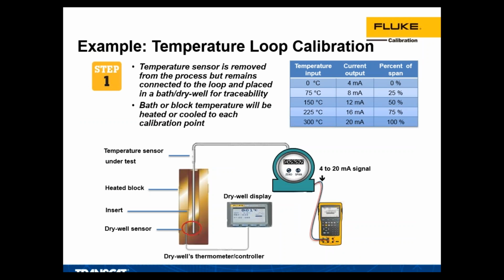So what does that entail? Well, first thing that we need to do is remove the temperature sensor from the process and put it into the dry block. It remains connected to the transmitter, and we connect the transmitter, the 4 to 20 milliamp output, to the 754. And what we're going to be doing is changing the set point temperature on the dry block via the 754. We'll have the temperature set points pre-programmed and a delay. So let's say we set it to every 20 minutes, it's going to change the temperature to a new temperature, wait 20 minutes, and then take a reading.